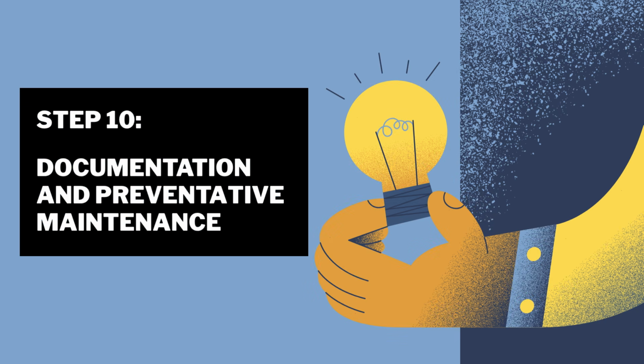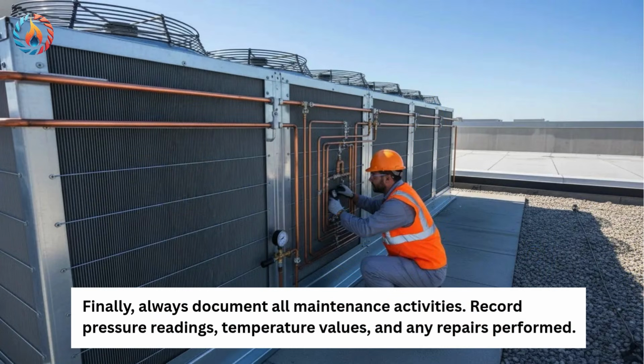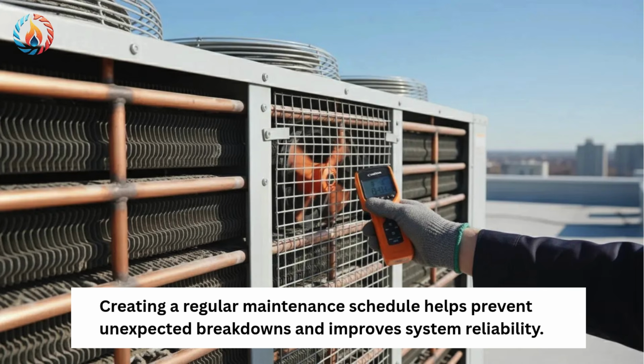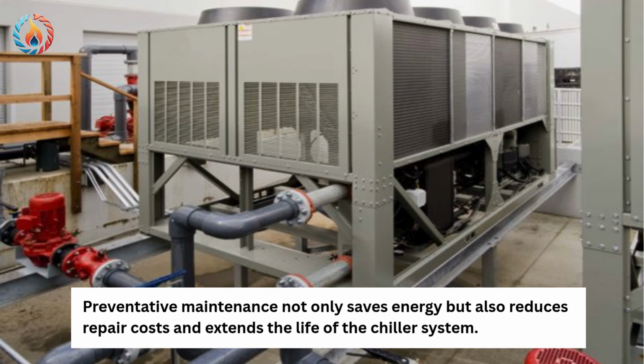Step 10. Documentation and preventative maintenance. Finally, always document all maintenance activities. Record pressure readings, temperature values, and any repairs performed. Creating a regular maintenance schedule helps prevent unexpected breakdowns and improves system reliability. Preventative maintenance not only saves energy, but also reduces repair costs and extends the life of the chiller system.